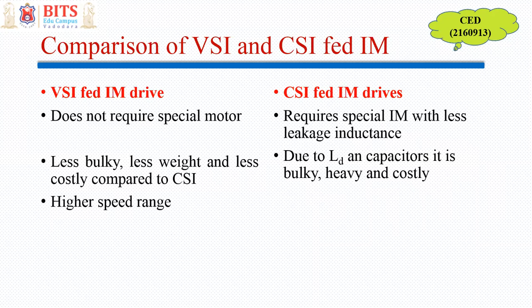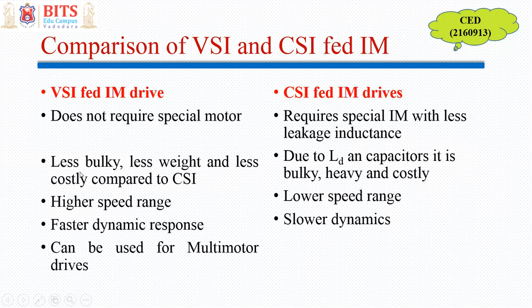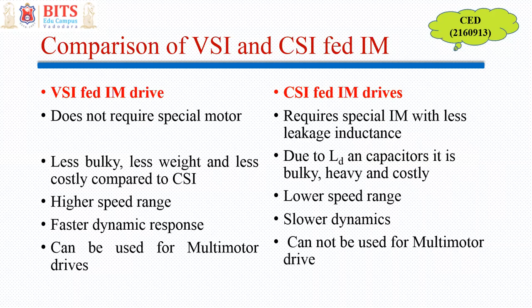VSI-fed induction motor drives have a higher speed range while CSI-fed have a lower speed range. Dynamic response is faster in VSI-fed drives while it is slow in CSI-fed drives. VSI-fed drives can be used for multi-motor drives while CSI-fed cannot — you need a separate CSI-fed inverter for each motor. In summary, for low and medium power applications VSIs are used, while for very large power ratings we generally go for current source inverter-fed induction motor drives. That's all for this particular topic.